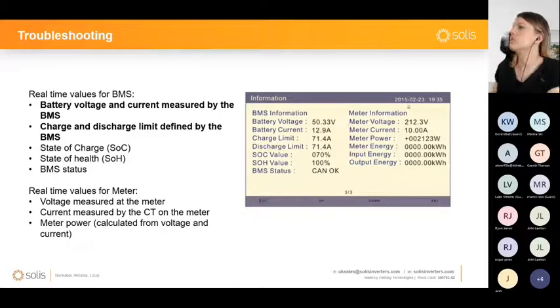And again, there's going to be a screen with the meter information. This will be helpful if you are trying to troubleshoot, for example, or to find out if that CT clamp is in the correct direction. This information here in the meter information is going to help you quite a lot, because here you're going to see a value for meter power, and that's going to be either a positive or a negative.